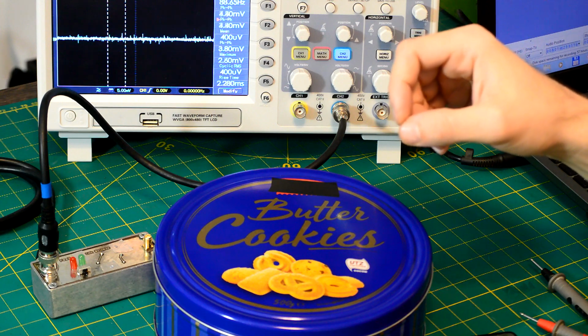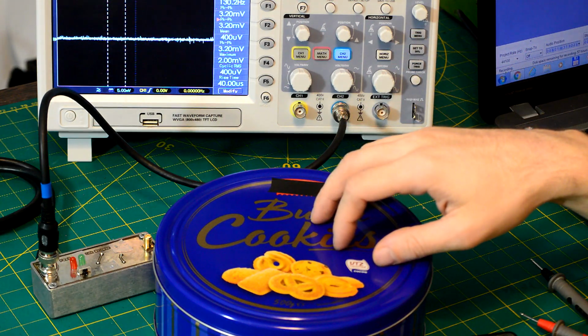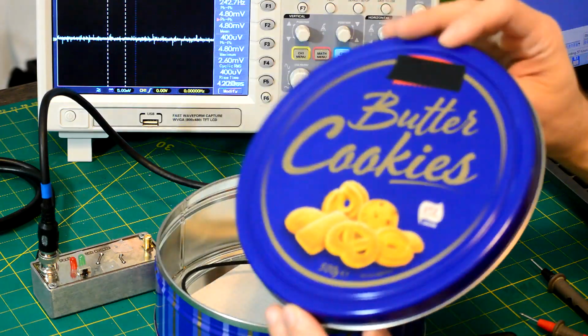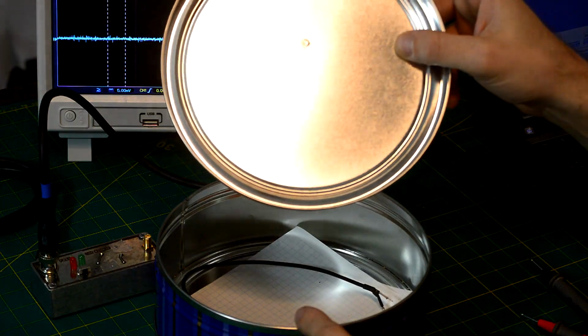Second thing you can look out for is the thickness of the walls. So the thicker it is, the better. Another thing to consider is grounding it. So you don't just need a metallic box, you need to have it connected to ground or to earth ground. And speaking of earth ground, you need to make sure that the lid is actually connected to the rest of the box. Let me show you what I mean.